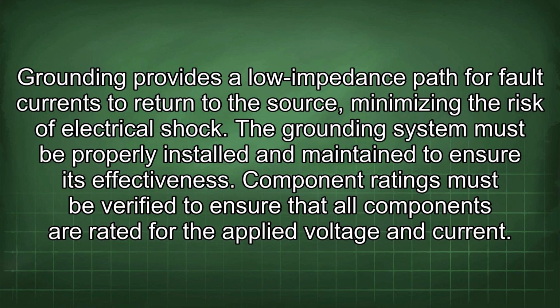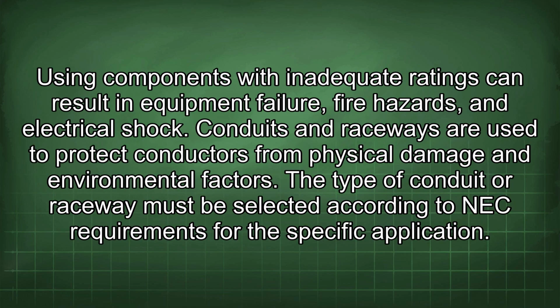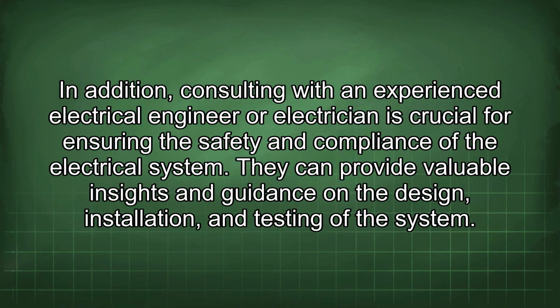Component ratings must be verified to ensure that all components are rated for the applied voltage and current. Using components with inadequate ratings can result in equipment failure, fire hazards, and electrical shock. Conduits and raceways are used to protect conductors from physical damage and environmental factors. The type of conduit or raceway must be selected according to NEC requirements for the specific application. In addition, consulting with an experienced electrical engineer or electrician is crucial for ensuring the safety and compliance of the electrical system. They can provide valuable insights and guidance on the design, installation, and testing of the system.